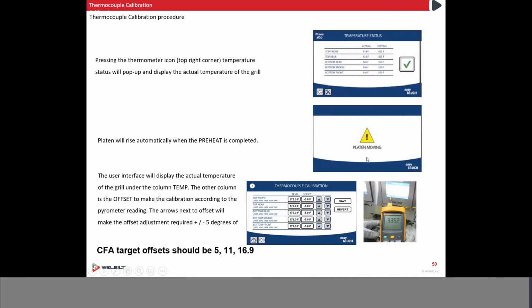We're going to wait until the Platen comes up. We're going to check it, and we're going to match our meter to the temperature to the meter by using the up and down arrows. Same process. What's different on this process is right here. The CFA target offset should be 5, 11, and 16.9. That's what they're looking at to see in the offsets. So again, that's your goal, to get close as possible to that with your temperatures.